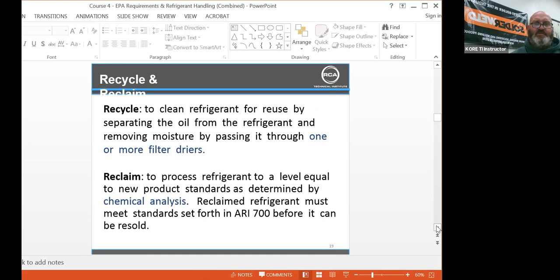Recycle is to clean refrigerant for reuse by separating the oil from the refrigerant and removing the moisture by passing it through one or more filters. Again, when you're going to do that, make sure that you're putting pre-filters on your recovery units like your Appions. They will actually burn up the seals if you're using bad refrigerant, or the oil will dissolve the seals, and it causes unnecessary repairs.